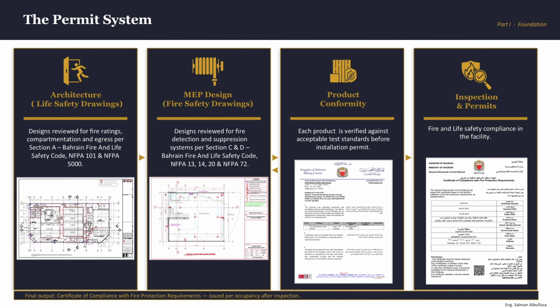And anyways, moving ahead to MEP design, sprinkler layouts, the fire alarm system, fire pump specifications, and smoke control, all of it must be reviewed and approved before a single pipe is installed. Because a sprinkler system designed to the wrong standard or the wrong spacing will not perform when it is needed. The review exists to catch those problems on paper, when change is just a revision, not on site when it means tearing down everything from the building.